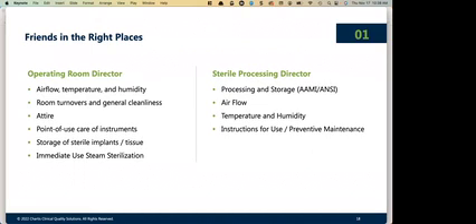And when we talk about instructions for use and preventive maintenance, where I find most problems are not with your annual or semi-annual PMs that are done by one of the large manufacturers, I'm trying not to mention names. They usually are pretty much on top of it. But it's the daily, weekly, monthly preventive maintenance in the instructions for use that would be performed by your sterile processing staff. We see that those things are often not being done because we do not know what our preventive maintenance schedules are. And so those are the big issues that I find in the sterile processing area, without going into a long dissertation.